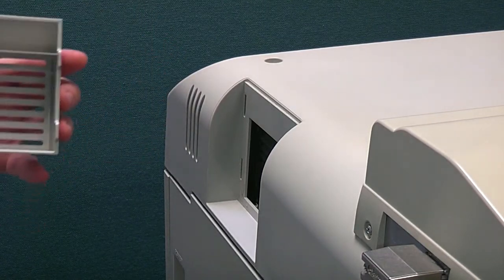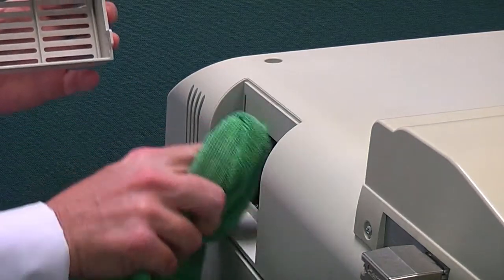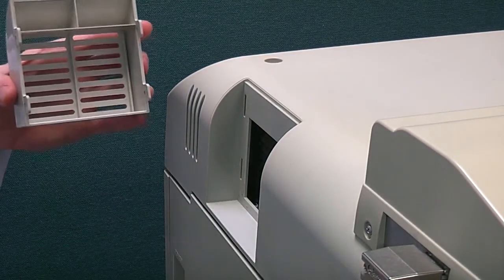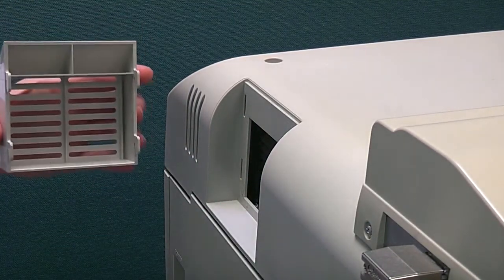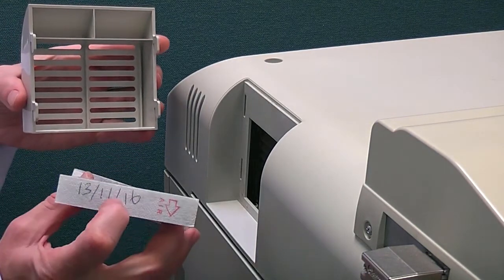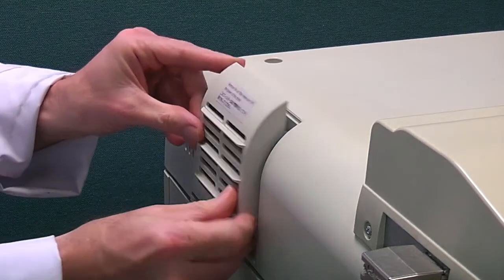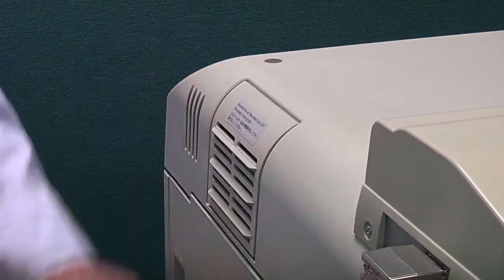Remove the filter holder and wipe away any dust. When fitting the new filter, write the date that it was replaced. Wipe the rest of the dryer unit.